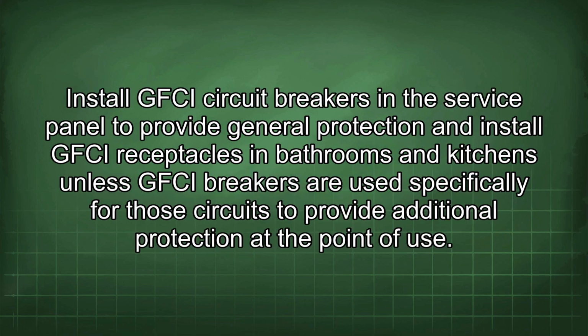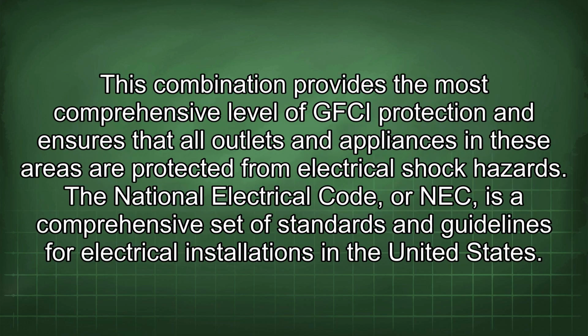Install GFCI circuit breakers in the service panel to provide general protection, and install GFCI receptacles in bathrooms and kitchens unless GFCI breakers are used specifically for the circuits to provide additional protection at the point of use. This combination provides the most comprehensive level of GFCI protection and ensures that all outlets and appliances in these areas are protected from electrical shock hazards.